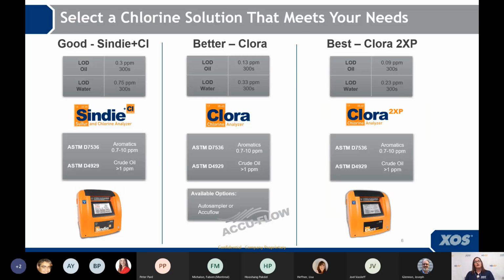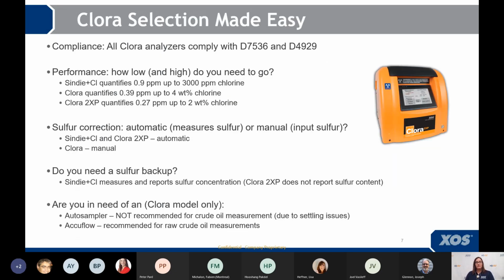Moving on to chlorine. You also want to select a chlorine solution that meets your needs. The analyzers here can be parceled into good, better, and best as well. And here's what you want to think about when you're selecting the correct chlorine tool for the job. First of all, compliance really isn't an issue because all of our Clora analyzers will comply with D7536, which is chlorine in aromatics, and D4929, specifically procedure C, for organic chlorides in crude oil. The most important thing here is you need to consider the performance. How low and how high do you need to go? Okay, this is before you consider autosamplers, AccuFlow, having a sulfur backup. It's very important that you pick an analyzer that will measure as low as you need it to.